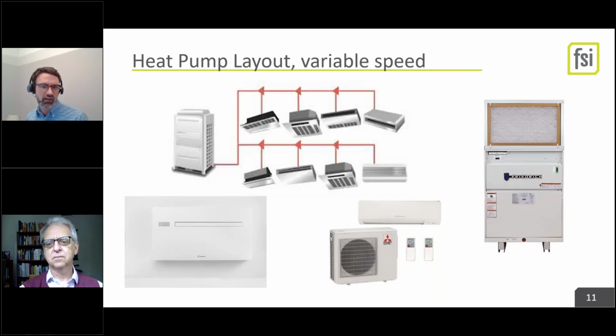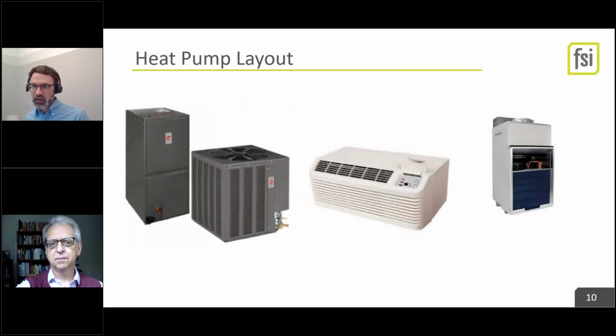There's a newer class of equipment out there, and it comes in all the same form factors, but it uses a variable speed compressor that does some magic with the hot gas of the refrigeration cycle, so it'll run down to super cold temperatures without using electric resistance, which, remember, electric resistance steps you back to 100% efficient. A heat pump can be, at peak efficiency, 300 to 400% efficient. We would also call that a coefficient of performance of 3 to 4. So if you hear engineers speak COP, it's really a way of saying it's more efficient than 100%. And that's just part of the magic of the refrigeration cycle, moving heat instead of creating heat like you do with electric resistance and things that you burn. Let's go to the next slide.